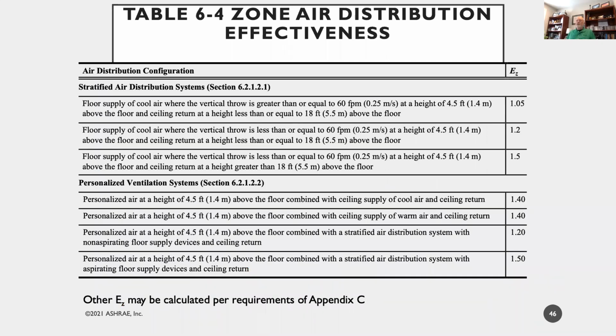So now what's in 62 that's different? What's in 62 that's different is this table has now changed dramatically from what it was for the 15 years before 2019. And now we said, oh, we've got these other things where the E sub Z, instead of dividing, reduces the amount of air. It's not subfractions. It's, oh, what if we have a stratified air distribution? What if we have something that's really like displacement ventilation? What if we have something that's like personalized air ventilation? And so I'm going to talk about what those things are, right? There's some of that's buried in the handbook, but there's some of it that's new ideas. So this whole idea of what do we do with the air and how do we move it around is really an important thing to understand.